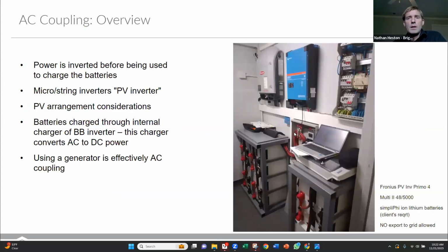AC coupling. Let's get into AC coupling. I'm showing here a Fronius inverter, which is connected to Victron equipment here. We've got a SimpliPhi battery bank underneath. Power is inverted before being used to charge the batteries. So what's coming into that charging equipment is actually AC, and the charging equipment is responsible for converting that back to DC, because charging the batteries, of course, requires a DC power supply to be able to charge up those batteries.